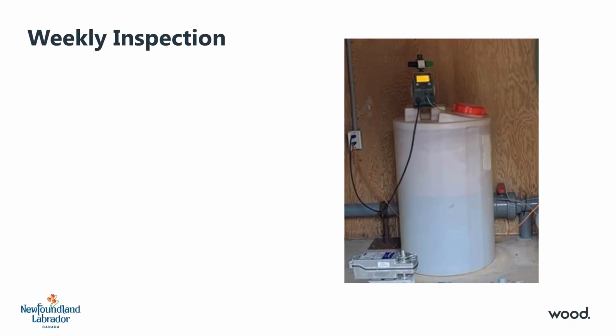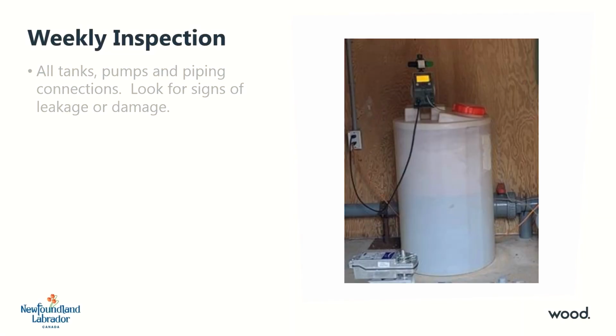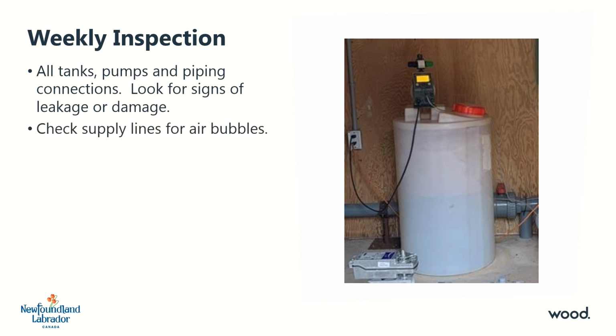In order to ensure that pump components are operating correctly and to avoid potential issues, inspections of the chemical feed pump system should be performed weekly. Weekly inspections should include the solution tanks, pumps, and connections. Operators should look for any signs of leakage or damage and check supply lines for gas bubbles. You should also listen for any unusual noise from the pump, as that may indicate replacement of a pump component is needed. Regular cleaning of pump components should also be conducted during regular maintenance activities.